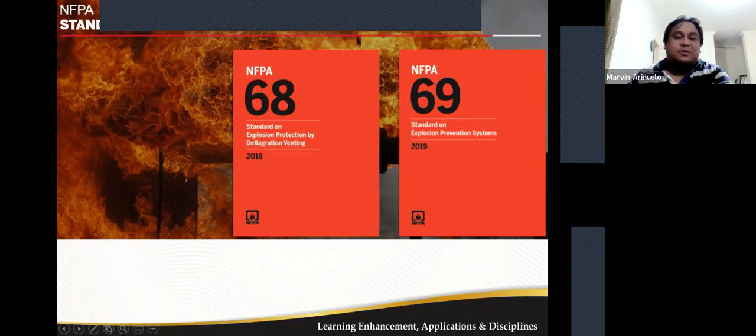Deflagration develops when a combustion reaction front propagates through a premixed fuel air mixture at a velocity less than the speed of sound in the unburned mixture. So probably if this will come in your exam: deflagration, fuel air mixture, less than the speed of sound. Detonation occurs when the reaction rate exceeds the speed of sound. An explosion develops when internal pressure from deflagration bursts or ruptures an enclosure or container.